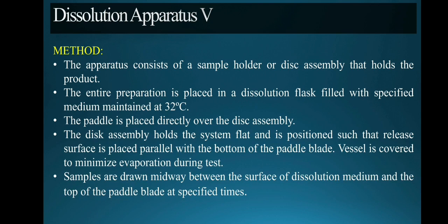The disc assembly holds the system flat and is positioned such that the release surface is placed parallel with the bottom of the paddle blade, and the samples are withdrawn from midway between the surface of the dissolution medium and the top of the paddle blade at specified times, which is same as the previous apparatus.